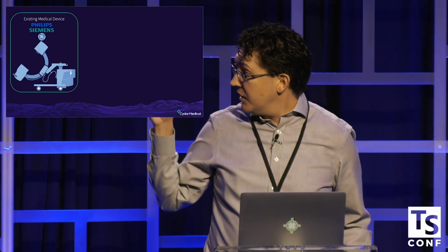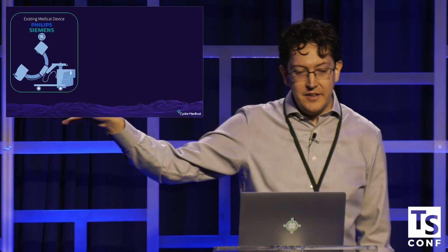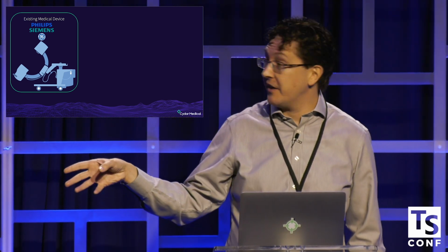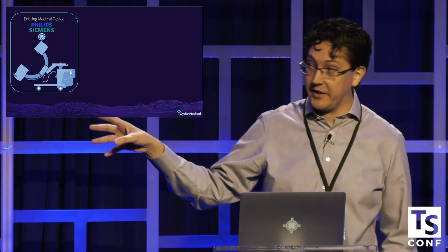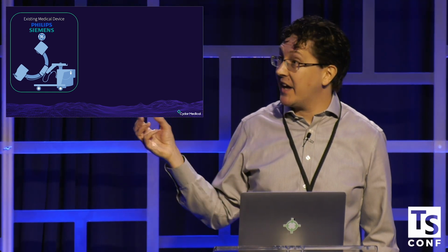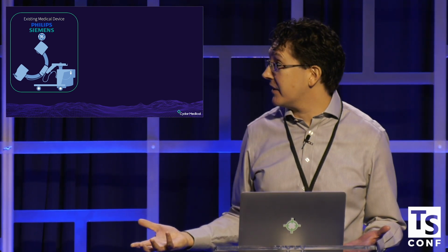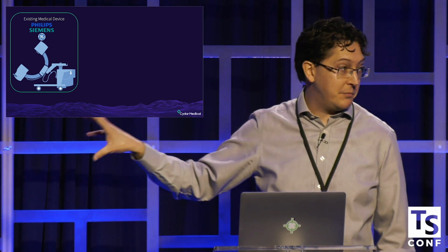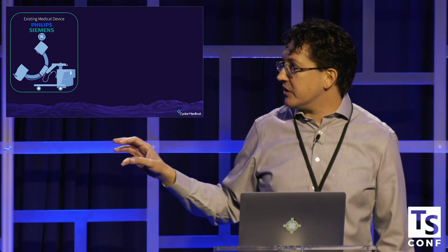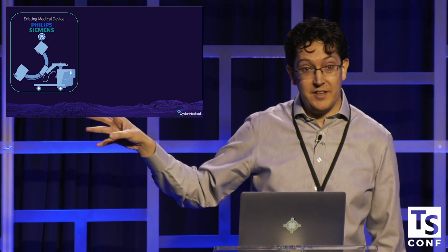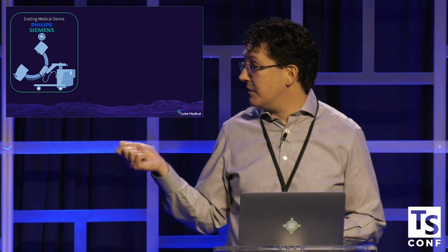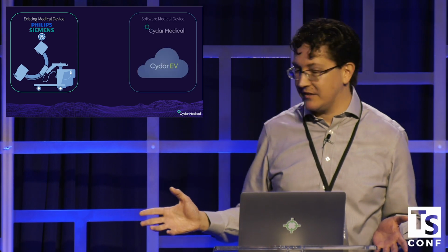So if I take you into the medical room, our setup is we have an existing medical device, the X-ray set. That is a classic medical device, for obvious reasons, because it's shooting ionizing radiation at people. That is very highly regulated. It's a very involved process to get the certification, and if you modify it at all, that would potentially invalidate the certification. So we don't do anything to modify that device. Fortunately, a standard feature on these is a video feed for a second monitor. So that's what we plug into our capture card, and we can access the pictures from that device without impacting its certification.